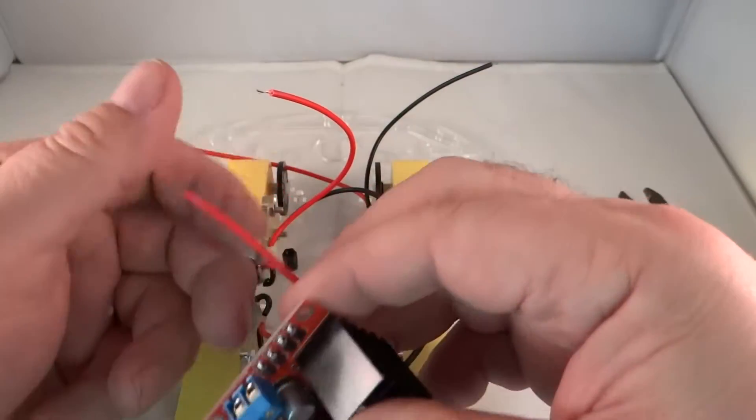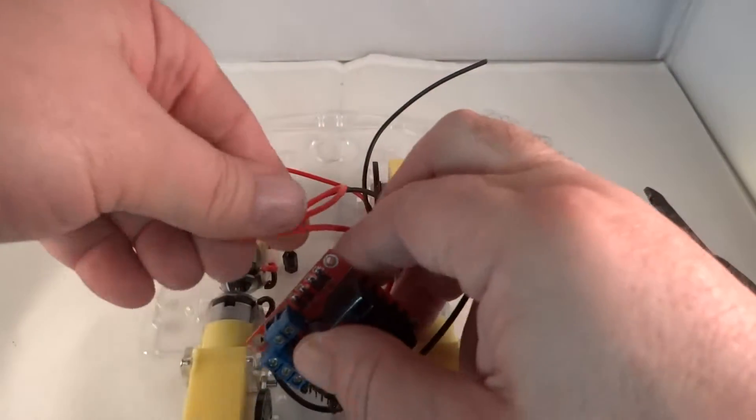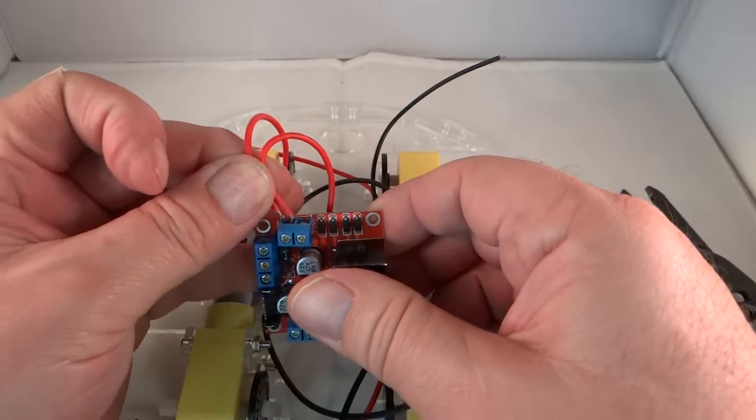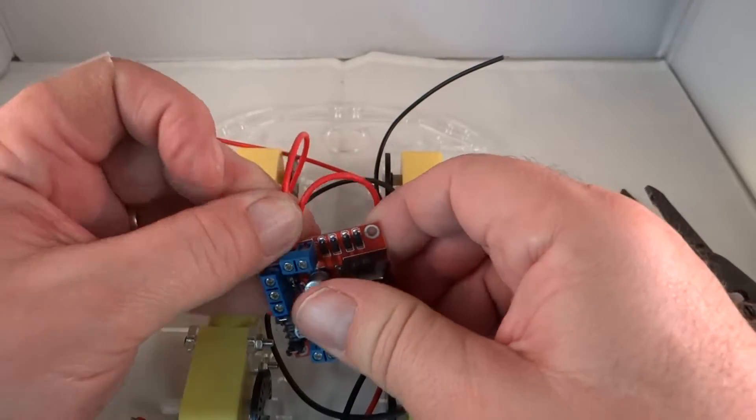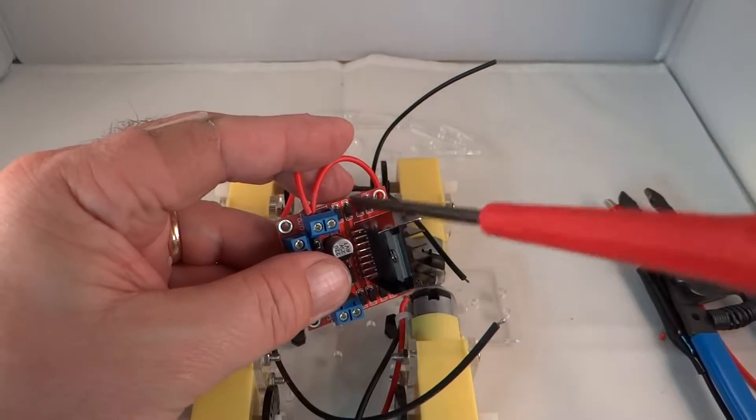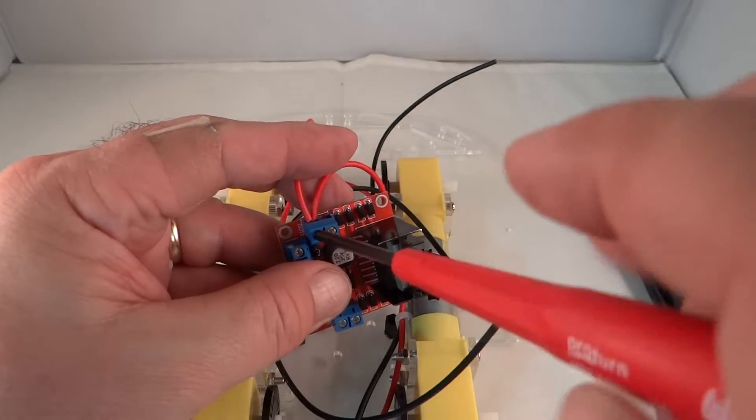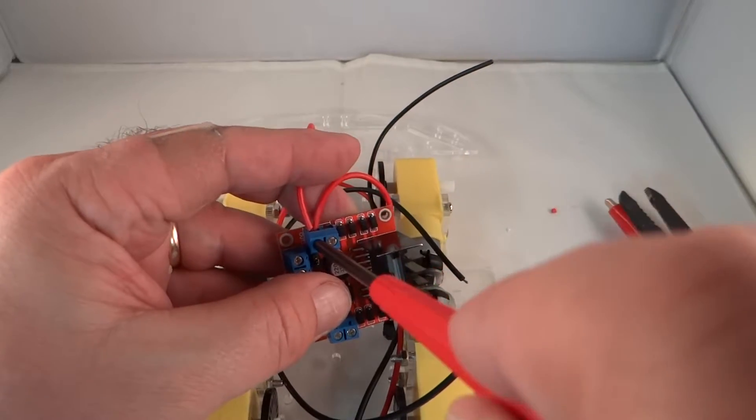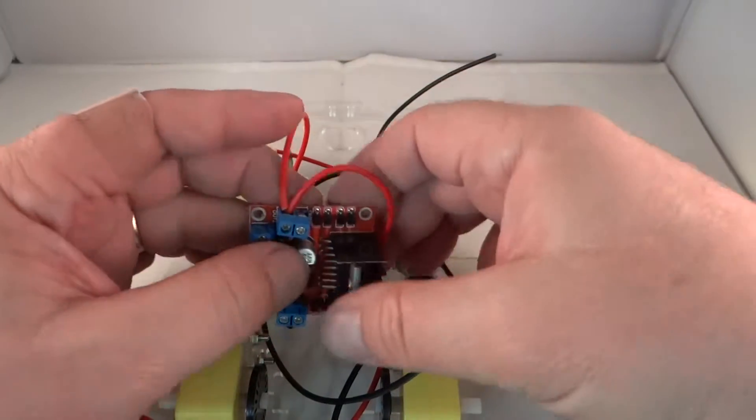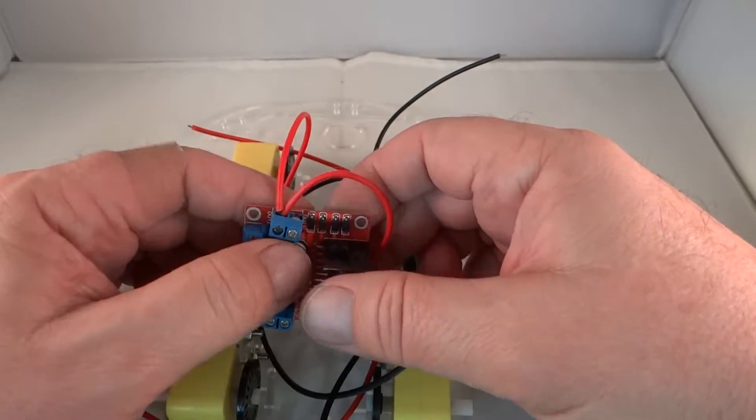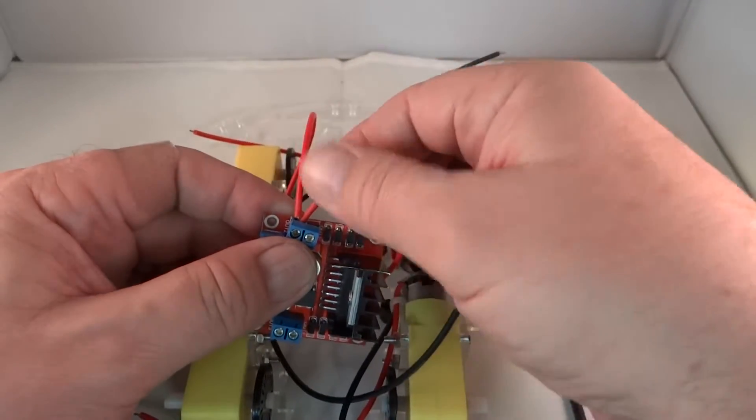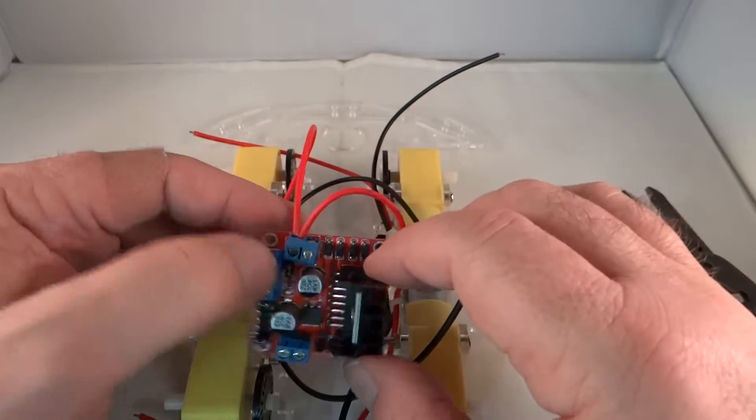So now that they're stripped, I am going to push both of them into this one connector. Push them all the way in, as far as you can go. And then you tighten them down. You don't want to use a million pound muscle there, but you do want to make sure you get it nice and tight. And then you do a pull test. Make sure that the wires won't come out.